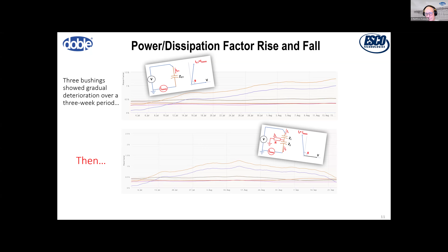So people say, hey, I got a negative power factor, does that mean my bushing is a generator now? The answer is no. It's probably got a lot of contamination or leakage somehow between the center conductor and ground, if you're doing what's called an ungrounded specimen test, which is essentially what a bushing test is for those familiar with that kind of test.